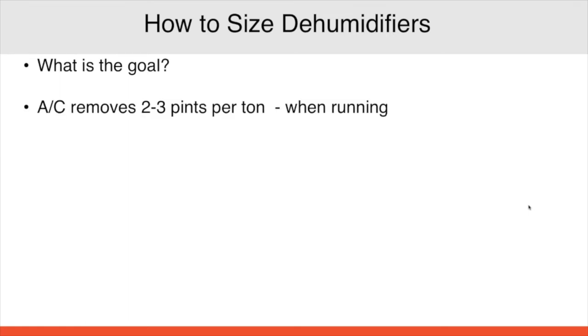So we know that the AC is going to remove approximately 2 to 3 pints per ton when running. So it has to be running for longer periods in order for that water to go down the drain. And then, how has that AC system been sized? Are we using Manual J and Manual S to get our calculations to know how that AC's been sized? Has it been oversized? Is it a little undersized? That's going to help us understand a little bit more how much latent removal we're getting from that air conditioner.